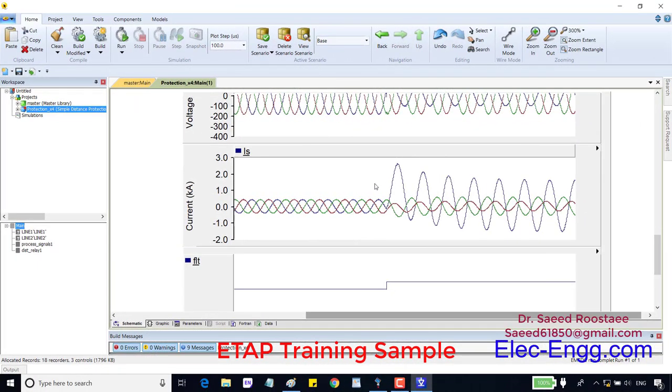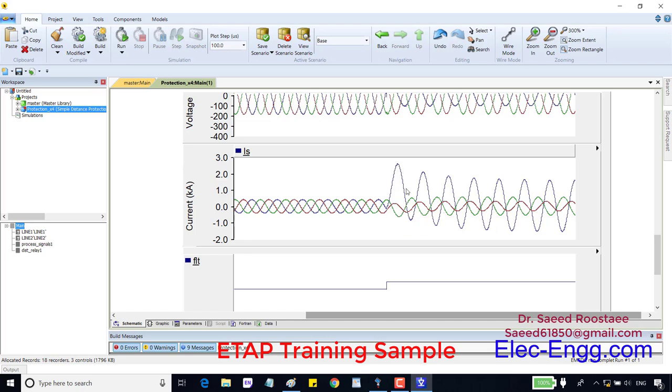Maximum fault or short circuit is approximately 2800 amps. Here is three phase current without fault, and AG fault happening at this time. As you can see, in the first half cycle fault current is maximum and the peak is also in this period. This period is called sub-transient time.